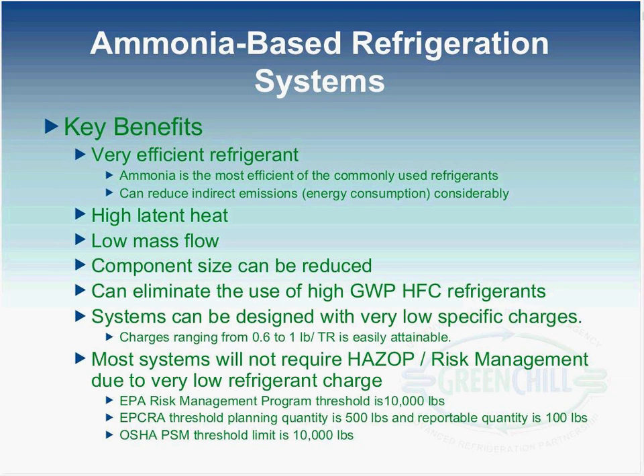Most systems using ammonia will not require any hazard or risk management because of very low specific charges, such as the EPA Risk Management Program threshold quantity of 10,000 pounds. Then EPCRA, the Emergency Planning and Community Right-to-Know Act, talks about a threshold quantity of 500 pounds, which translates into the system size. You're looking at a 6 million BTU refrigeration load. That is not the size of a typical supermarket.